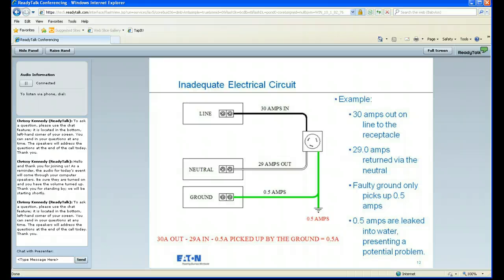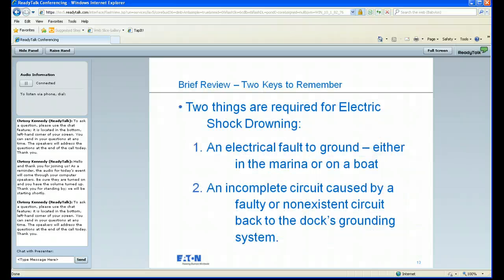In a faulty system, using the exact same example, we're going to have 30 amps going out, and let's say the neutral line only picks up 29 amps. The ground may have some sort of issue in it here where it's cut, it's pinched, could be loose connections, could be a variety of things that are causing that neutral to be inadequate, but that results in half of an amp here entering the water. And that half of an amp is what causes problems such as swimmers being injured, props being damaged, certain things like that.